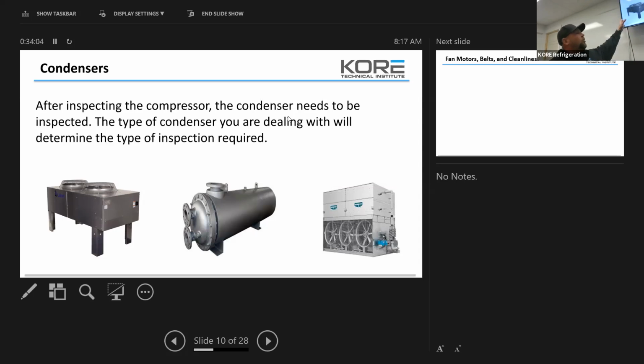Condensers. So this is an air-cooled condenser. This is a shell and tube condenser. This is an evaporative condenser. We see towers down in Phoenix, Vegas, hotter areas. We'll see a lot of towers with buildings where they're confined spaces. Air-cooled condensers usually take a bigger footprint as far as area, and you get a little bit more efficient cooling out of a water-cooled. The only thing about water-cooled is you've got to do some treatment in certain areas, or what we call the copper bundle turns into a rock really quick if it's not treated correctly.